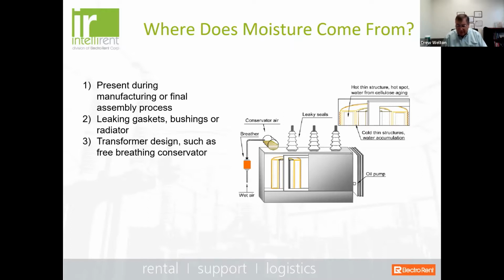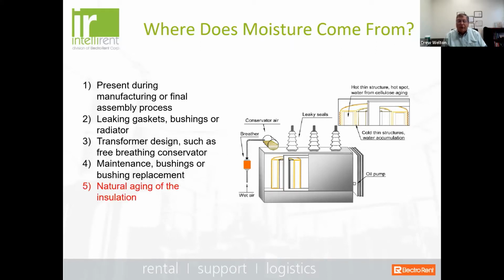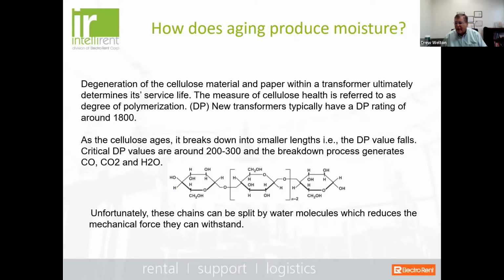Well, one of the things that you have to be cognizant of is the fact that moisture can come from the natural aging of the insulation itself. And this is very important to understand. So how does this happen? Well, as the cellulose material in the paper in the transformer starts to deteriorate, the resin bonds will start breaking apart. And chemically, the byproduct of these resin bonds breaking down happens to be moisture.